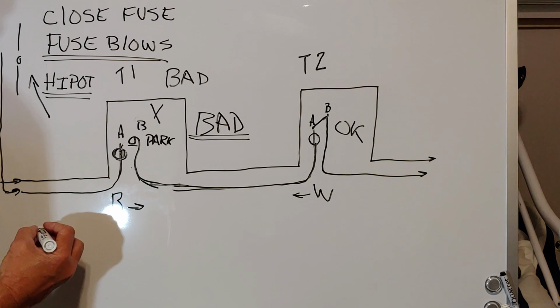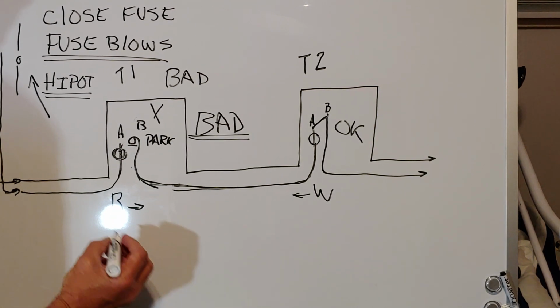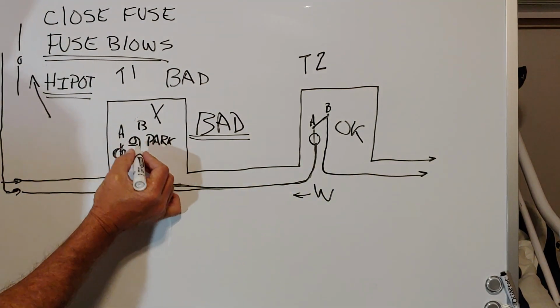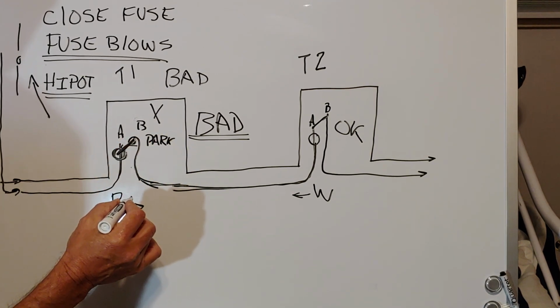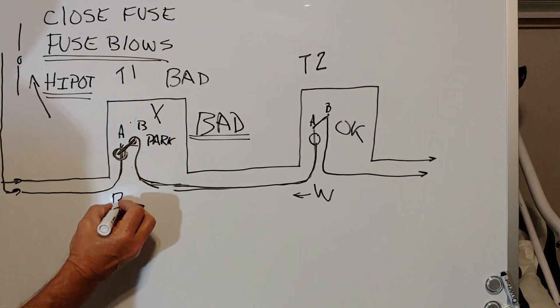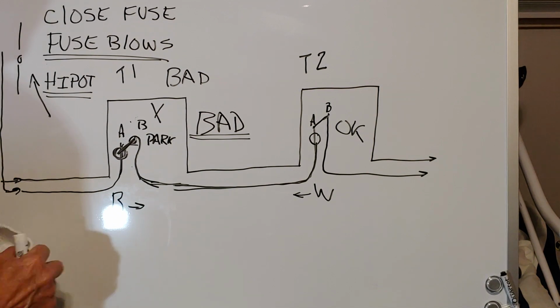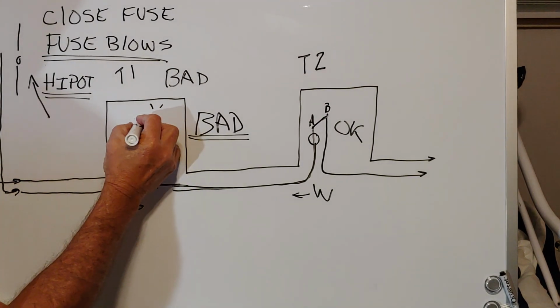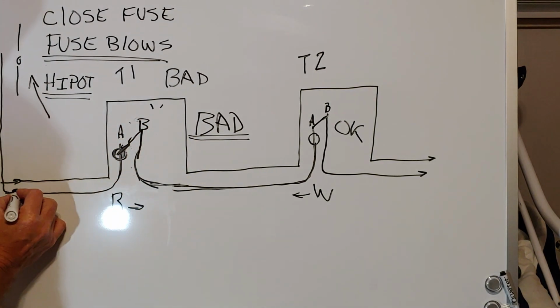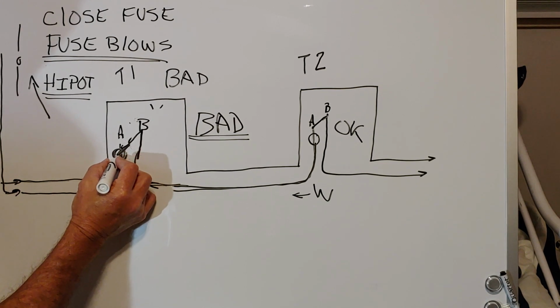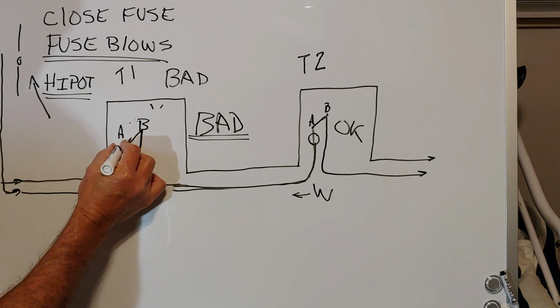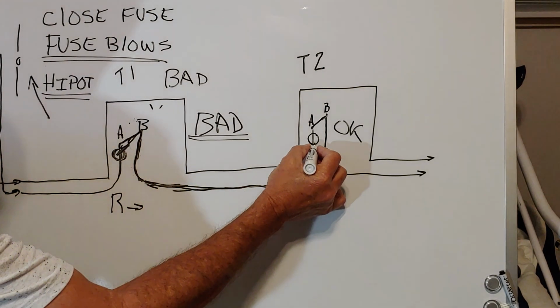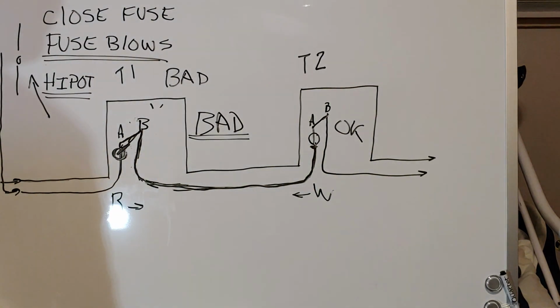All right. Just want to give you that added information right there that, you know, fault indicators are not only indicating or showing a fault on the cable, the transformer is in the mix here too. The windings of the transformer itself. So if we have a fault indicator at this location, and I'll get some of this out, get this back to normal. The fault indicator, primary feeds in A. The fault indicator from this point and beyond is seen here. The transformer itself, any faults inside that may have occurred, and the cable, all the way up to the next fault indicator where it stops. That's all it's looking at right here. Here to here, inside the transformer, up to here and stops.